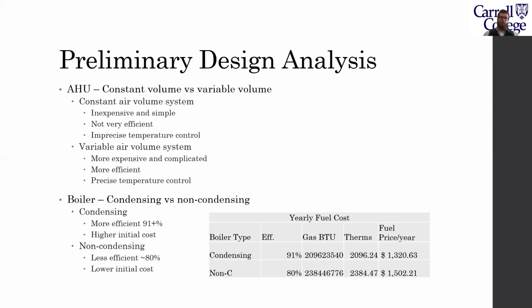There's 2 types of boilers, condensing and non-condensing. A condensing boiler is more efficient. It's 91% or more efficient usually, but it does have a higher initial cost. A non-condensing boiler is less efficient at around 80%, but has a lower initial cost. I ran a cost analysis on the 2 types of boilers, and a condensing boiler is about $180 cheaper per year for fuel prices. Over the 25-year lifespan of a boiler, this amounts to about $4,500, which would more than make up for the initial cost of the more expensive condensing boiler.